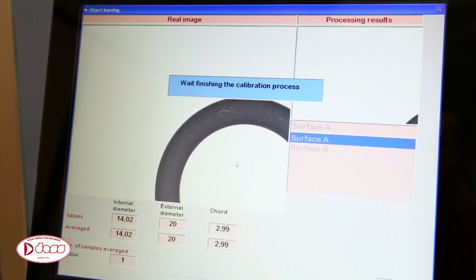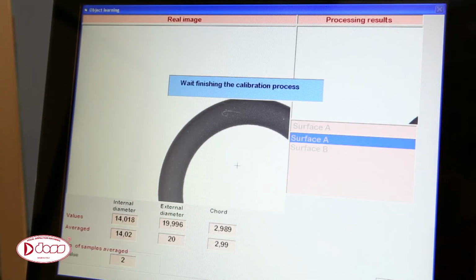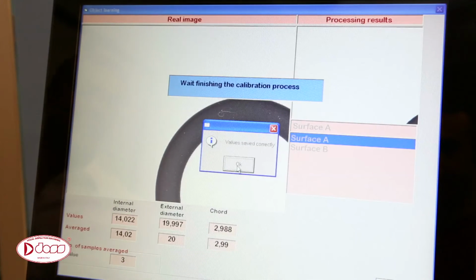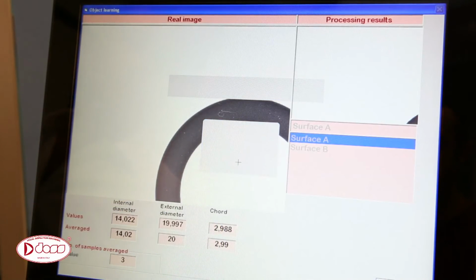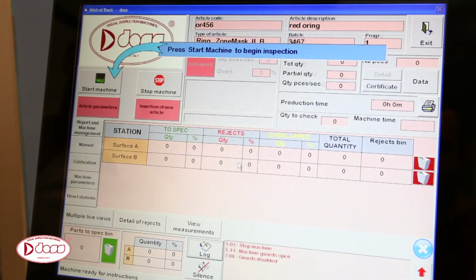After that, since it's a new item, the machine starts a calibration procedure. Since we're not touching anything, this calibration is only to confirm the dimension we're performing, and the machine starts this procedure automatically. It makes this routine 3 times at least, just to confirm that the system is running very well. After this, the software tells you that everything is okay. This way, the inspection can start.